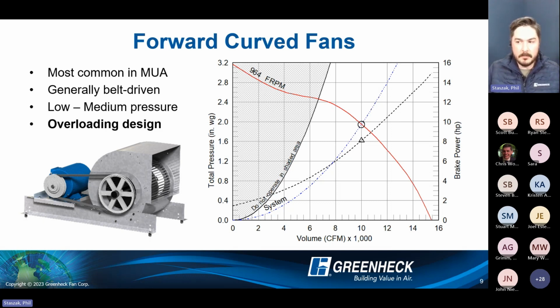But unfortunately, we see this all the time where ductwork or safety factors are built into it, or people just throw a 1/4 inch on it as a just in case. The problem is we set up the unit to hit a certain fan RPM and hit the design CFM that it was actually selected at. So we're trying to account for that static pressure.